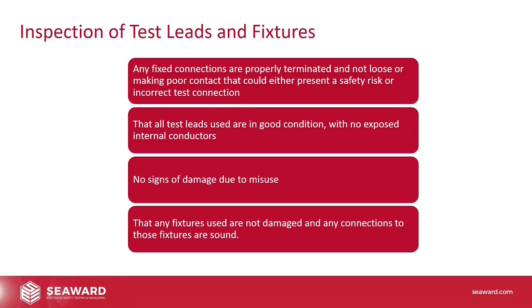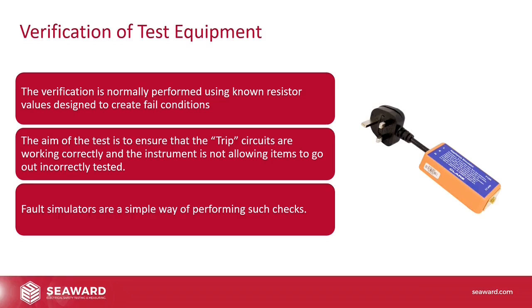That needs to be dealt with first, which is why tests have things like visual tests. This is very similar to a visual test if you're actually testing equipment. We want no signs of damage or due to misuse or anything else, really. We want to use really good condition equipment. If there's any damage to it, it could have damaged the insulation and could potentially cause an electric shock. That any fixtures used are not damaged and any connections to those fixtures are sound. So check your equipment, check your whole area for any damage or anything that could cause a shock. Really important. Inspection of test leads and all the fixtures.